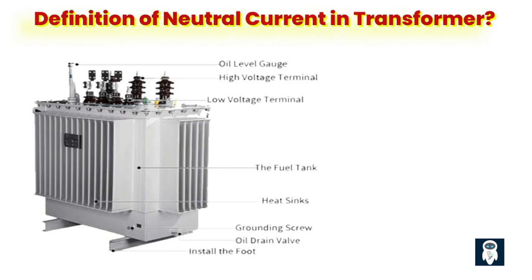Neutral current transformers are also used in protective relaying systems to trip circuit breakers in the event of a system imbalance. In addition, they are used in power quality analysis to measure harmonic currents in the neutral conductor. Harmonic currents can cause power quality issues such as voltage distortion and overheating of equipment, and by monitoring them with a neutral current transformer, these issues can be identified and addressed.